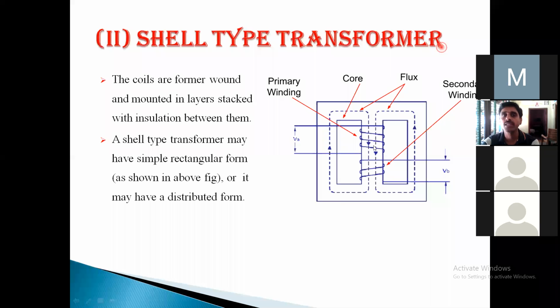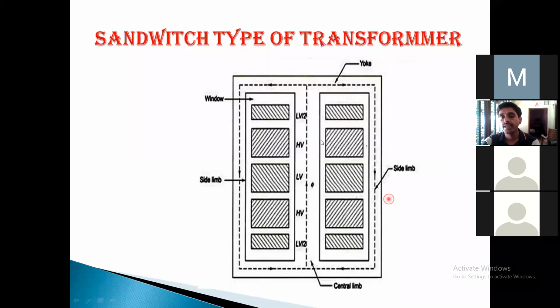Coming to the shell type of transformer, coils are former wound and mounted in layers like this, stacked with insulation between them. May have simple rectangular form like this, as shown. It may be a distributed form like this. The winding can be distributed. So sandwich type of windings, because winding will be inside, the core is surrounding the winding. Here is a central limb. So here low voltage, high voltage, low voltage, high voltage, like that. The windings will be sandwich, means layer by layer you can keep.